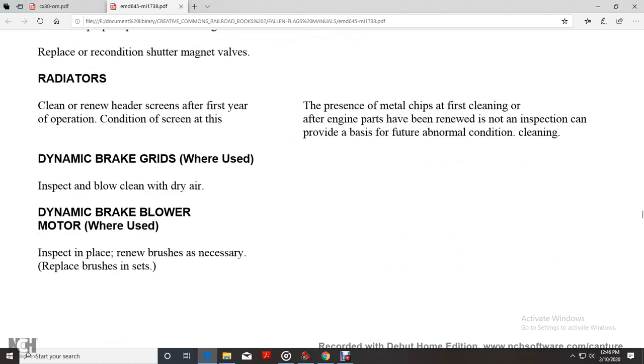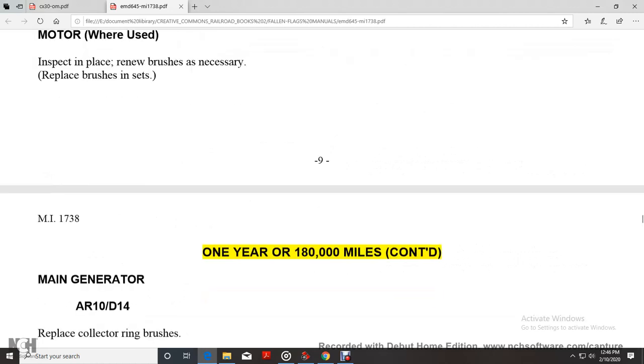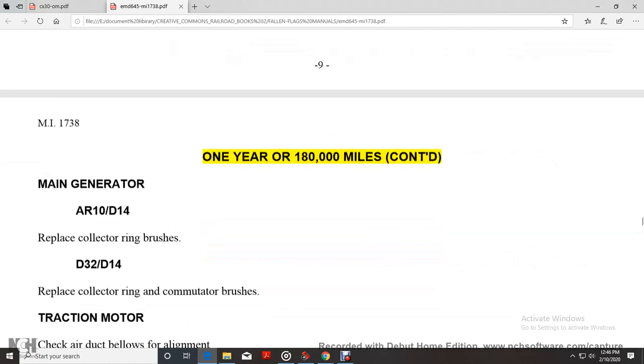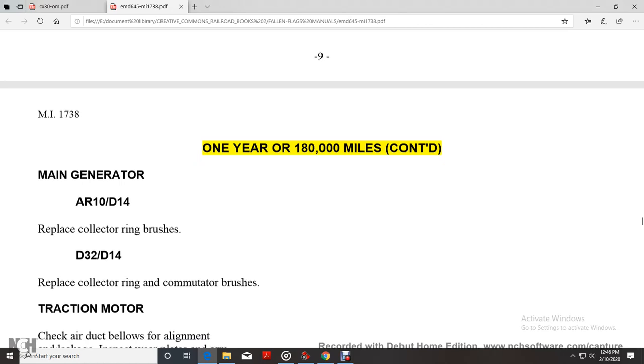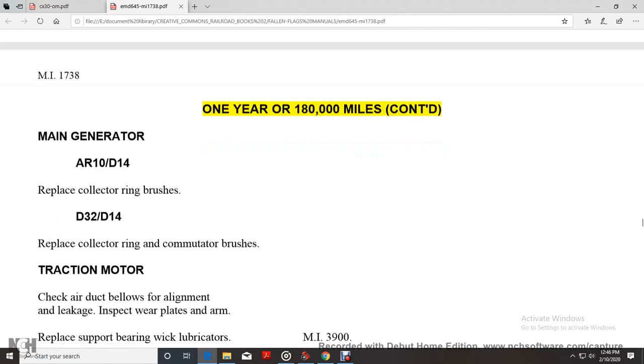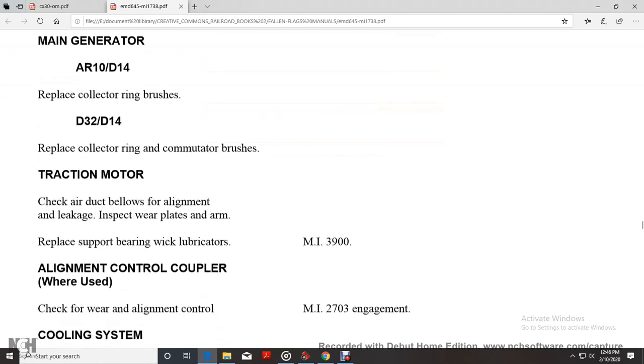Dynamic brake grids where used: inspect, blow clean with dry air. Dynamic brake blower motor where used: inspect, replace or renew brushes as necessary, replace brush set. One year, 180,000 miles continued. Main generator AR10, D14: replace collector ring brushes. D32, D14: replace collector ring and commutator brushes.